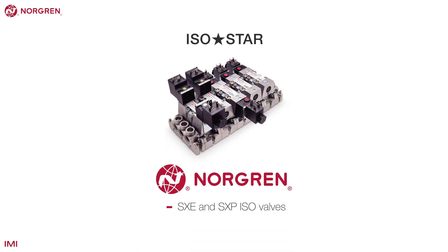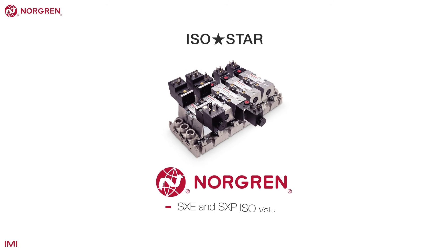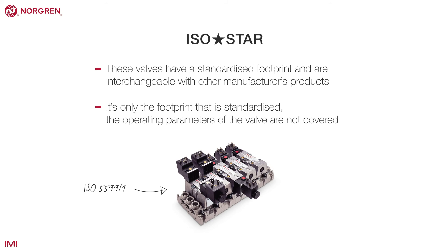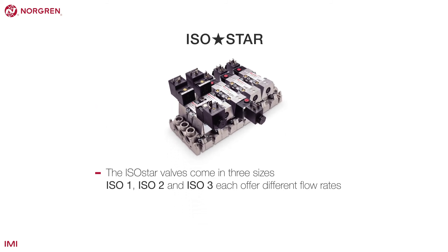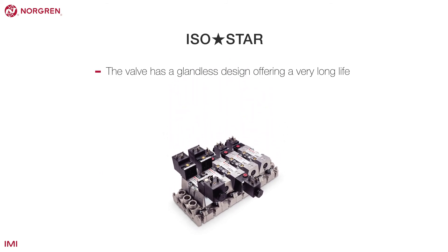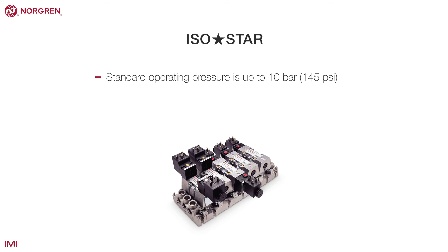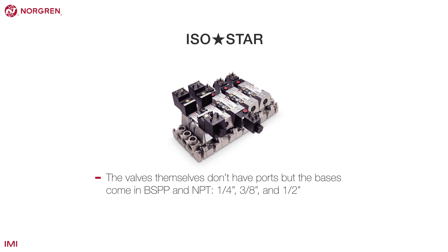ISO-Star is Norgren's range of SXE and SXP ISO valves. The ISO standard means these valves have a standardized footprint and are interchangeable with other manufacturers' products — it's only the footprint that is standardized though, and the operating parameters are not covered. ISO-Star valves come in three sizes: ISO 1, 2 and 3, each offering different flow rates; size 4 is available in the UM22000 series. The valve has a glandless design offering very long life with fast, accurate, repeatable switching. Standard operating pressure is up to 10 bar or 145 PSI, but external pilot or higher power solenoid versions can operate up to 16 bar or 232 PSI. The bases come in BSPP or NPT in quarter-inch, three-eighths and half-inch sizes.